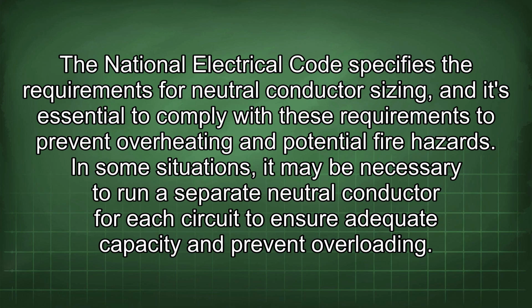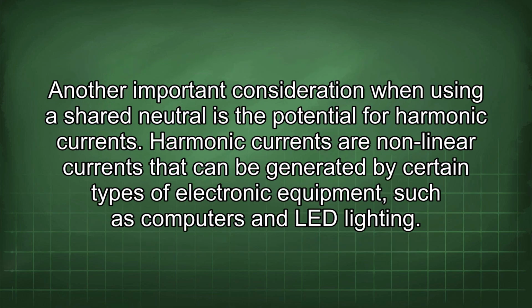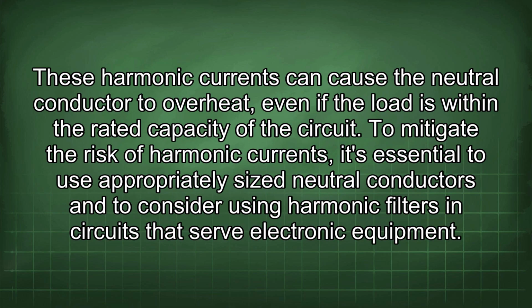Another important consideration when using a shared neutral is the potential for harmonic currents. Harmonic currents are nonlinear currents that can be generated by certain types of electronic equipment, such as computers and LED lighting. These harmonic currents can cause the neutral conductor to overheat, even if the load is within the rated capacity of the circuit. To mitigate the risk of harmonic currents, it's essential to use appropriately sized neutral conductors and to consider using harmonic filters in circuits that serve electronic equipment.